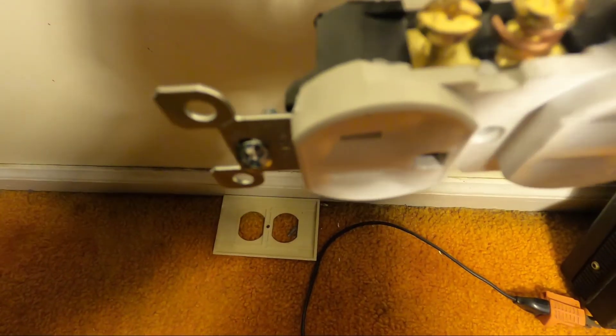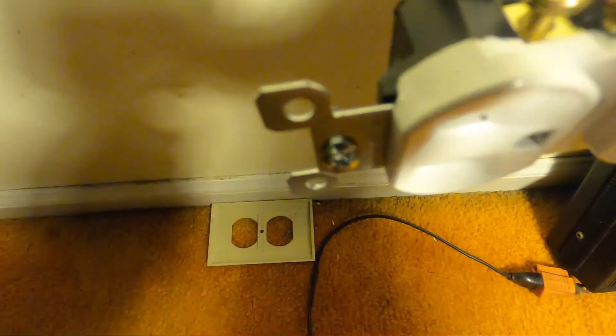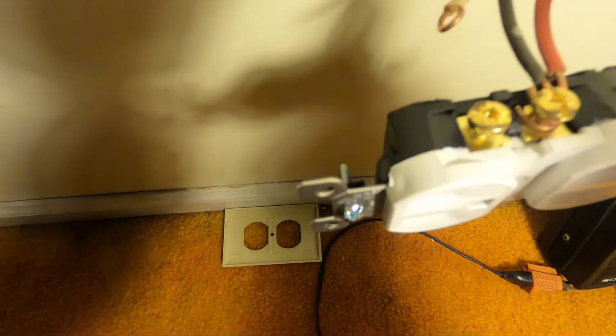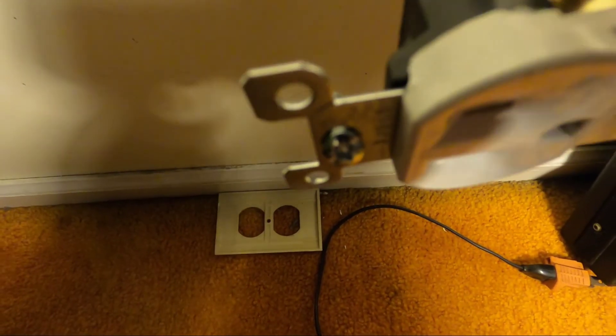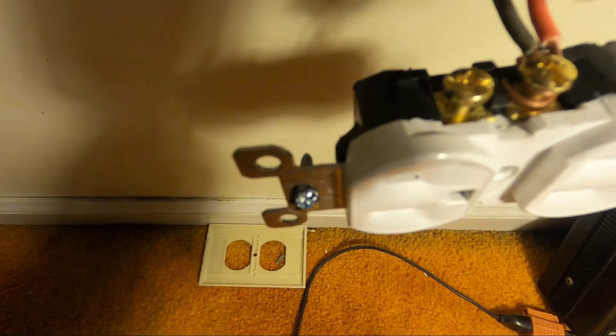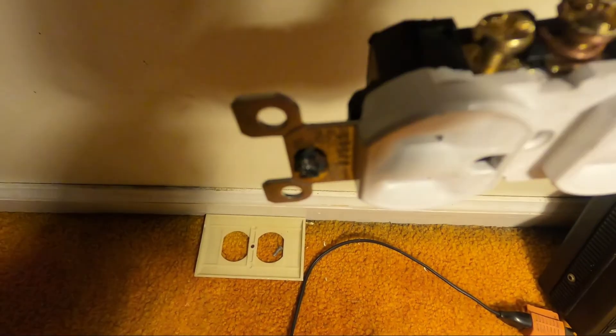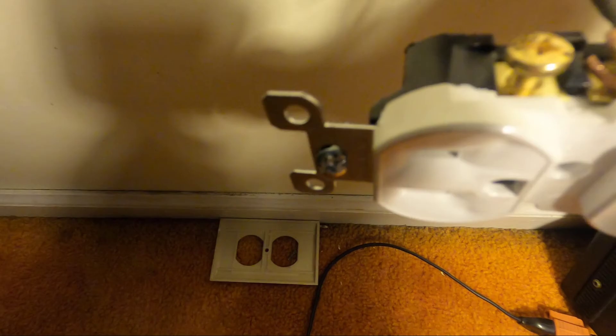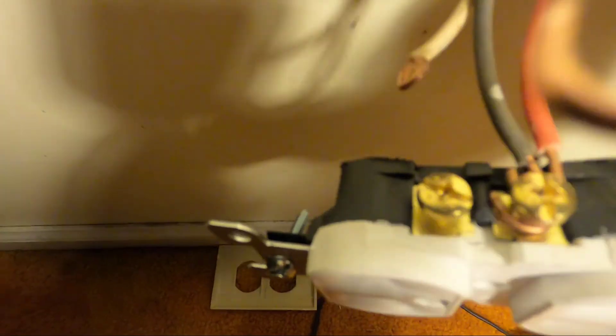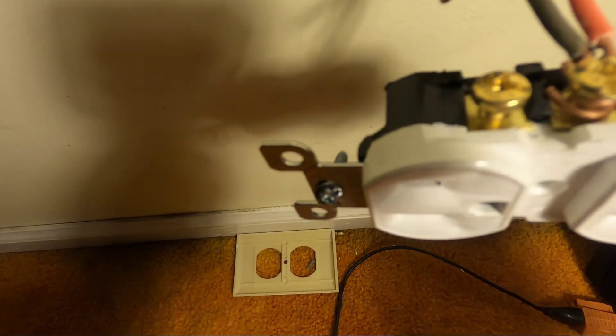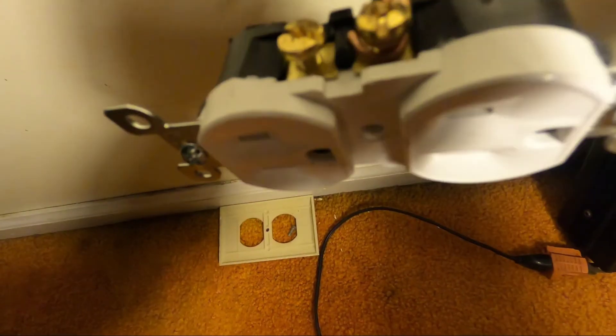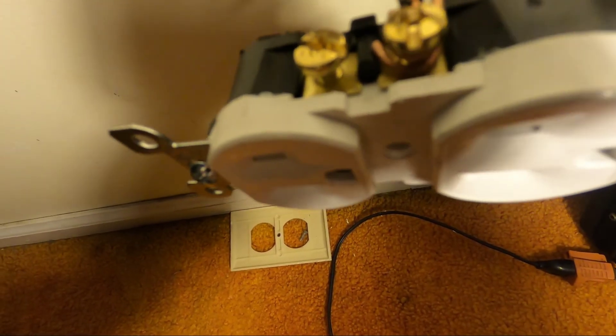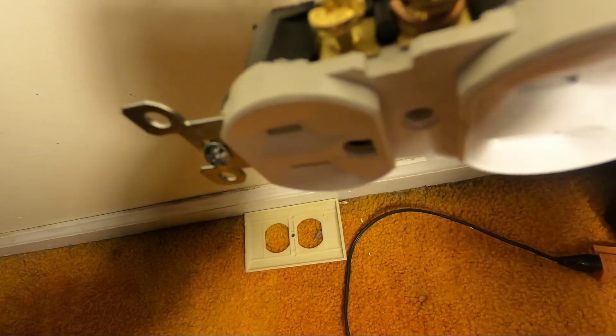So when these wires come in, this loop on the end of the wire, two things you want to make sure of. One, the loop is opened in the direction that the screw turns. This way, as you turn it, it's tightening it up and not opening it up. And you want to make sure this insulation over here, this insulation isn't under the screw. So you can make a nice, tight fit.